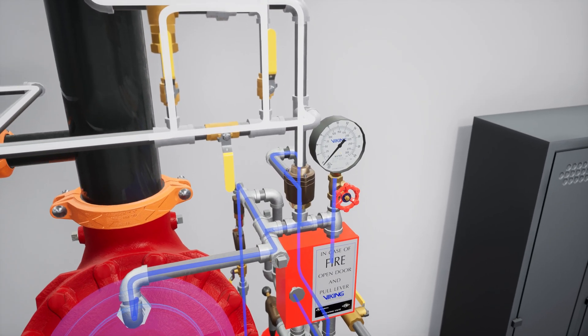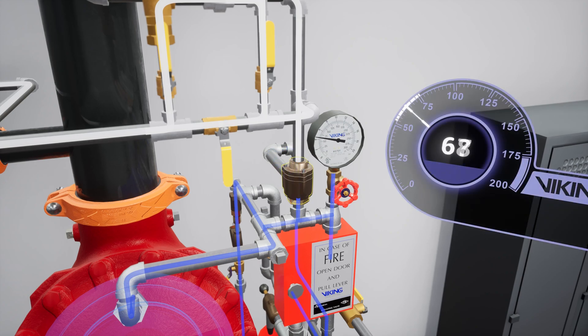After reestablishing air pressure in the release system, the pneumatic actuator will reset and allow water pressure in the prime chamber to build. Check to make sure water pressure is building in the prime chamber.